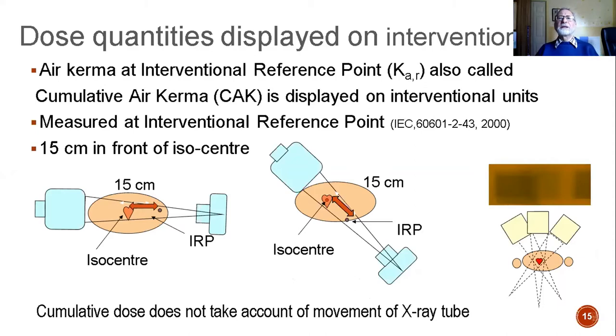So what quantities have we got? Well, the dose displayed on interventional units is the air kerma at the interventional reference point, also called the cumulative air kerma. The interventional reference point is 15 centimeters in front of the isocenter, so it approximates to the position of the skin. It gives an indication of the air kerma in the center of the beam at the position of the skin throughout an examination.